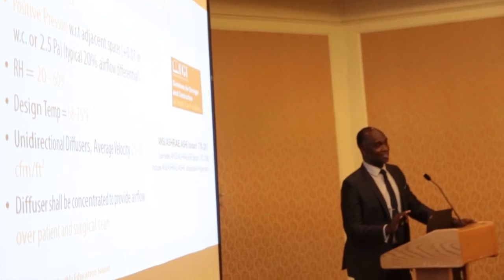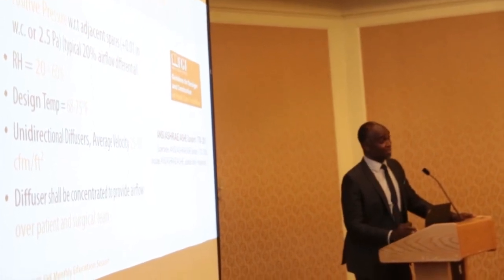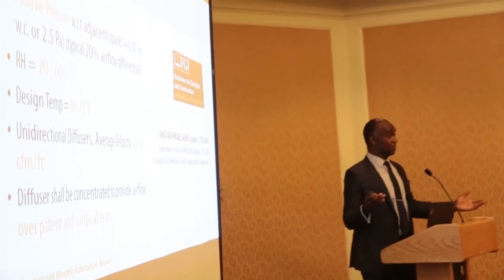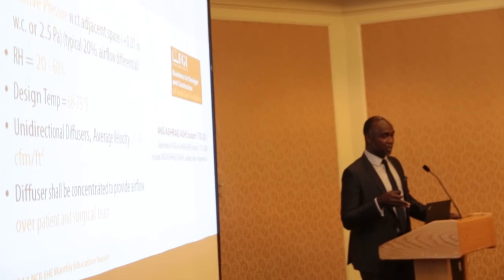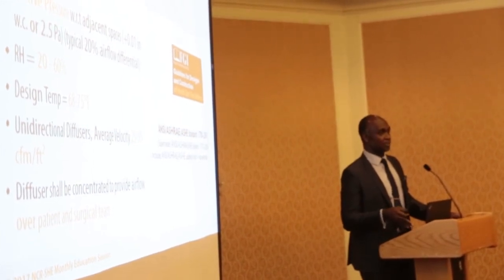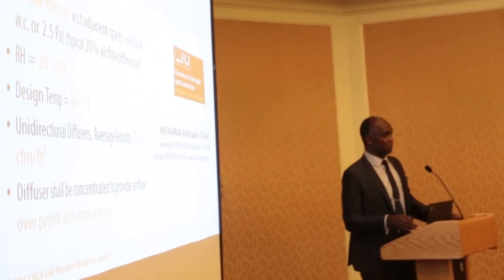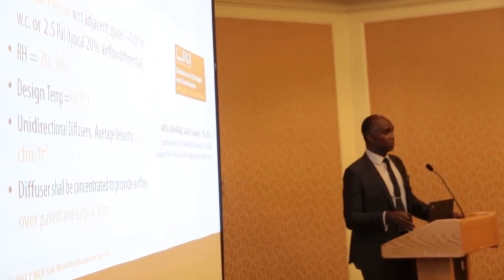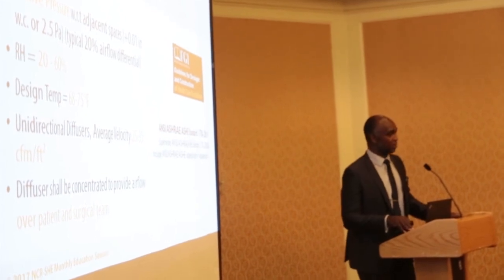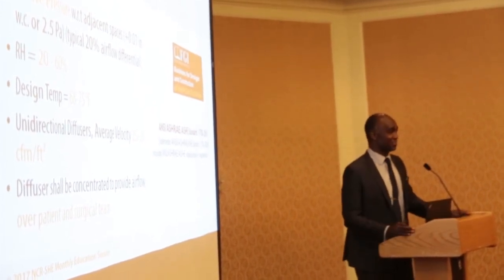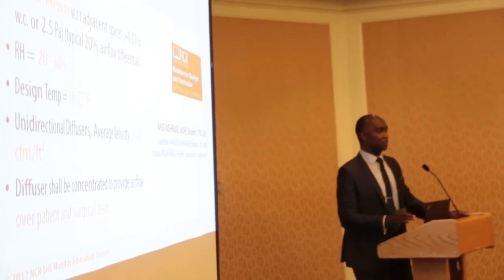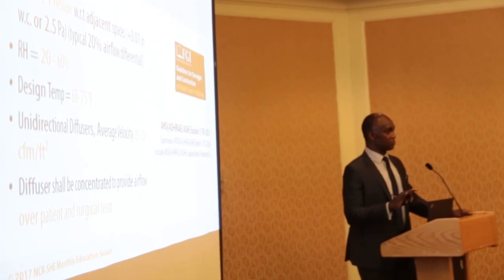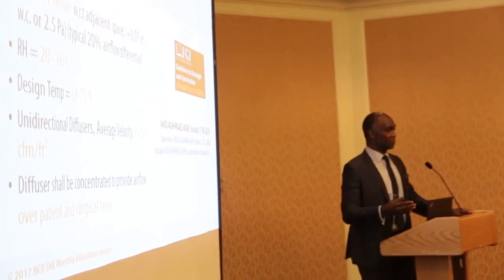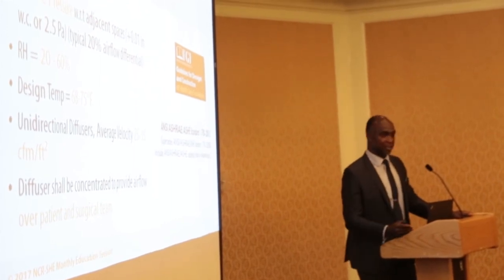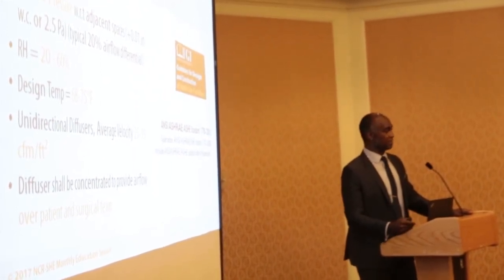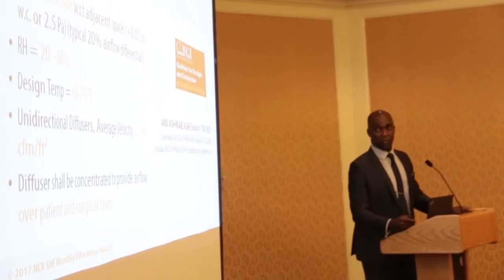Minimum means it could be 30 or 40, but for a hybrid OR, the equipment in your space dictates your load and the number of people in your space. When you calculate your actual HVAC loads, it's usually more than 20 air changes anyway, so most of these spaces are 25 to 30 air changes. They're just describing the minimum requirement, to make sure you change the air as much as possible so you can remove the bacteria, microorganisms, and viruses entrained in the air within the space.